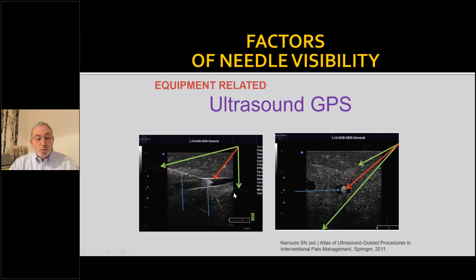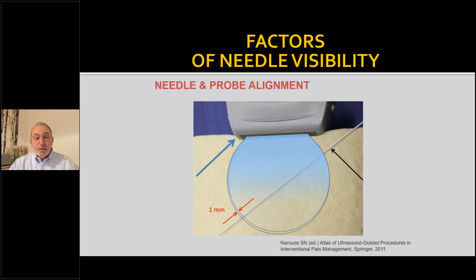This is very important, maybe the most important part, when you align your probe with your needle. The ultrasound beam is not that big. It's not like the probe. The probe is probably half an inch, but the beam itself is only about 1 millimeter. It's credit card size, and that's why it's important to have good alignment of the probe. Otherwise, you'll not be able to see it well.